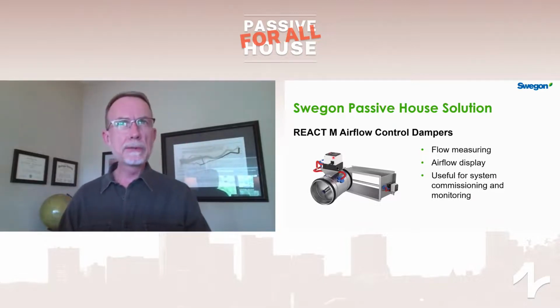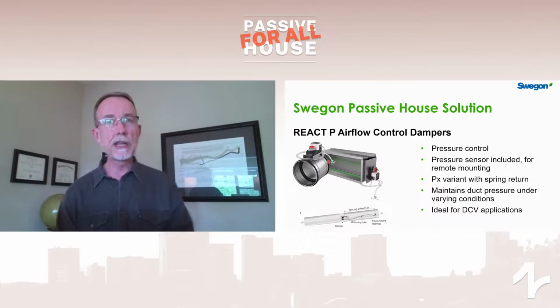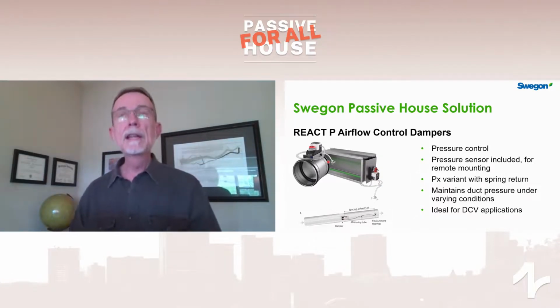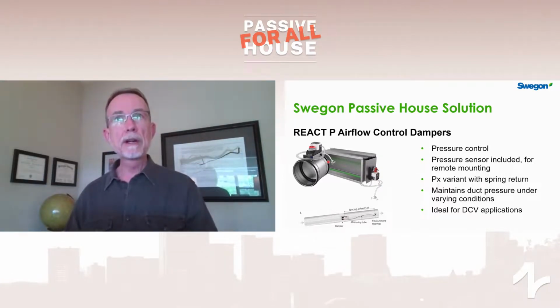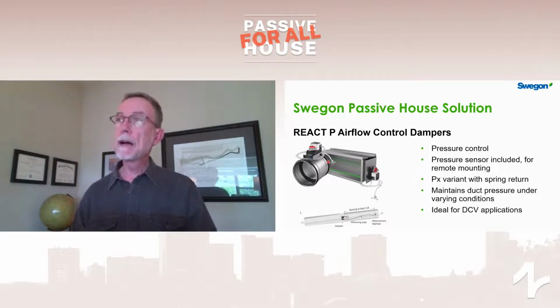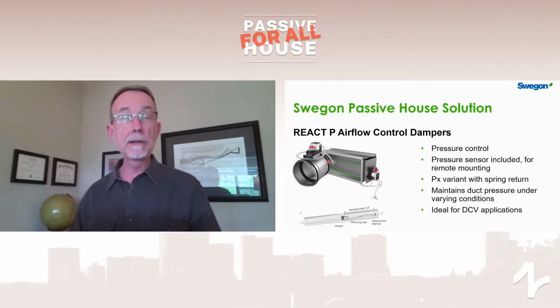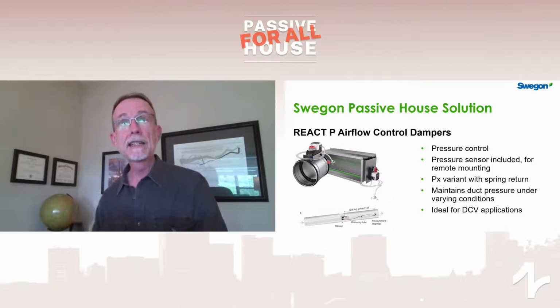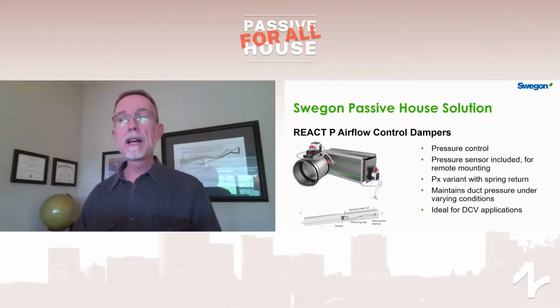Pressure control dampers are useful for keeping long duct runs or long shafts in balance as things change. So if you have a 20-story building served by one shaft, as apartments are occupied and unoccupied, or if you're in an office building, as zones become occupied and unoccupied, the flow rates can change, and that impacts the pressure level in the duct. And to keep that duct pressure constant, you can use the React P.